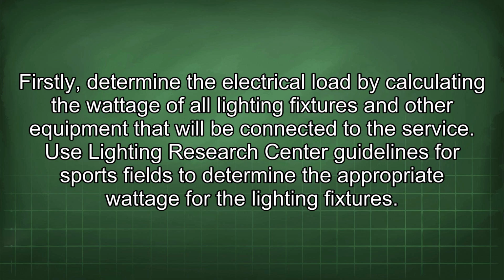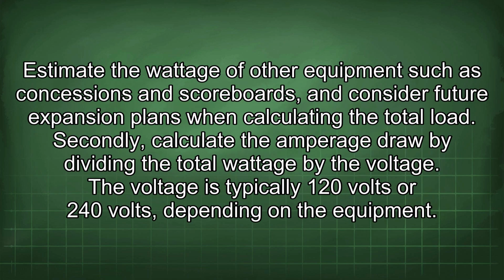Firstly, determine the electrical load by calculating the wattage of all lighting fixtures and other equipment that will be connected to the service. Use Lighting Research Center guidelines for sports fields to determine the appropriate wattage for the lighting fixtures. Estimate the wattage of other equipment such as concessions and scoreboards, and consider future expansion plans when calculating the total load. Secondly, calculate the amperage draw by dividing the total wattage by the voltage. The voltage is typically 120 volts or 240 volts, depending on the equipment.